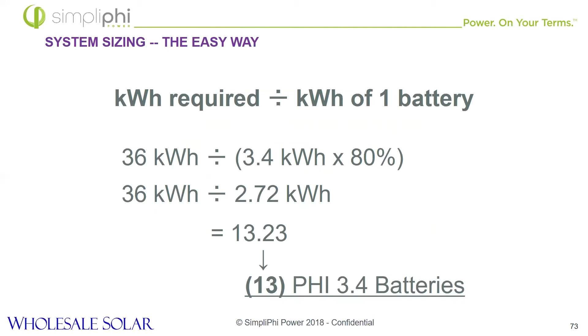The better way to do it is by pointing out that we really only want to take these down to 80% depth of discharge, to abide by that 10-year, 10,000 cycle warranty. So here's the actual calculation: you want to divide by 2.72, which is 80% of 3.4. In essence, 11 batteries is what you'd calculate that way, but a better calculation would be 13 in this scenario, and the same holds true with amp hours.